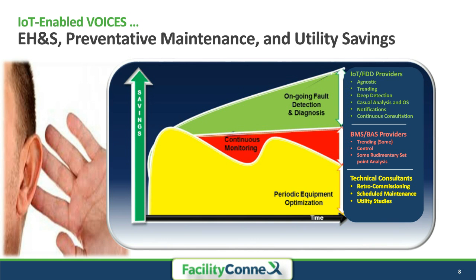Well, what monitoring-based commissioning does, every day, in real time, is this ongoing fault detection and diagnostics. It acts a little bit like the guy who analyzes the BMS data - it sits right on top of that system. It drives fault detection, but more importantly, it predicts the actual failure, and it tells you the cost of what it's costing you not to fix that problem. It's a very simple concept, but bringing that information together, you get back to that balancing.